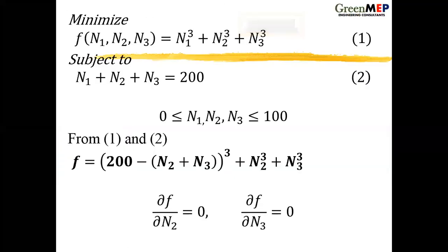Now, what is happening in building analytics software? We know that this is just a simple example, just 3 cooling towers, but when it comes to real systems, there can be a large number. It's not 3. It can be 20, right? Fans, pumps in one system, and so what happens is there's some mathematics going on. Let's take an example 3 cooling tower case. Assume they are not identical, or you're going to adjust the speeds. The software is going to adjust the speeds.